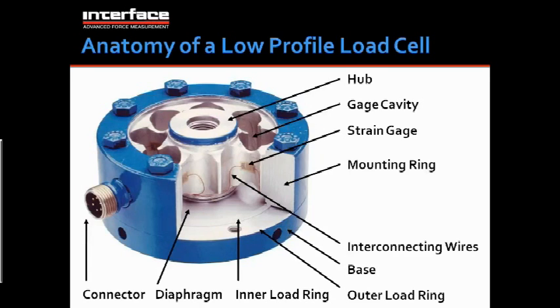Okay, next question. Do low-profile load cells have to have bases? Great question. I'll take that. Hello, this is Scott Dunn. Generally, we recommend that a load cell is shipped and prepared with a base. We try to maintain 2 10,000ths of an inch, or 0.0002, flatness on those bases and on the load cell. So when they're bolted down, the load ring or the mounting ring shown in Albert's anatomy of a low profile is flat and not twisting. Any of that twisting would show up as extraneous strains and then a force on that load cell. So shipping it with a base guarantees that the flatness is right, and then the load cell will not deflect simply by the mounting of it.